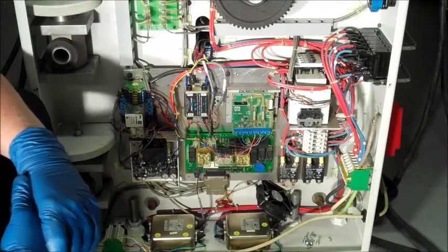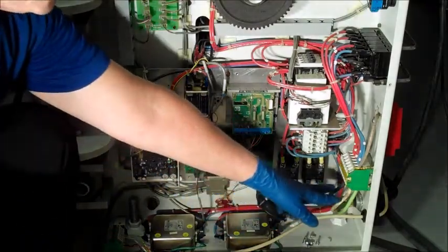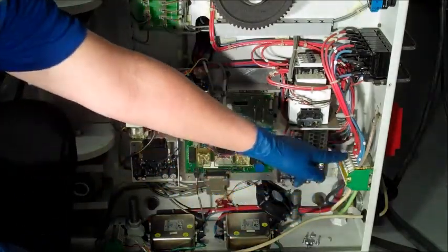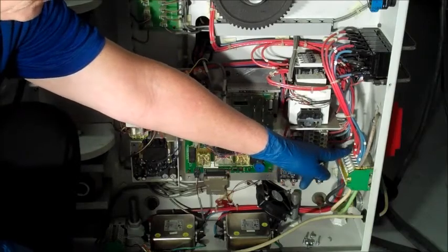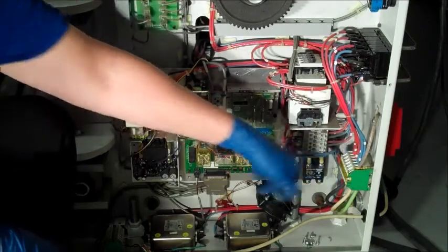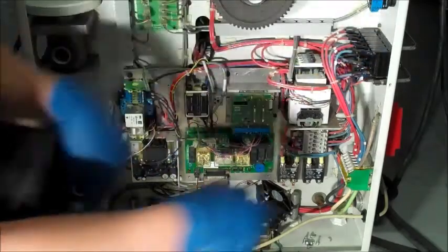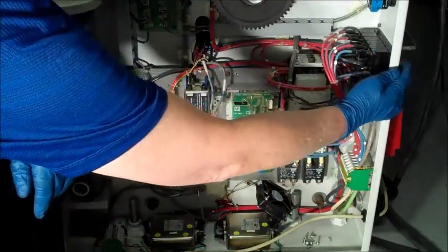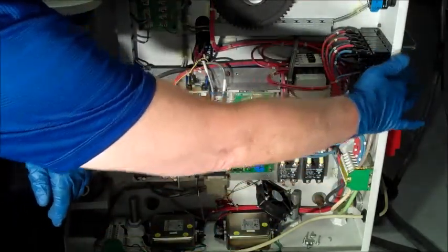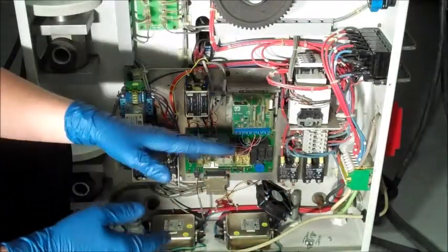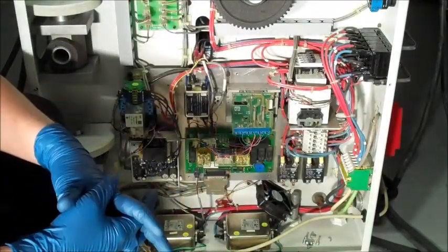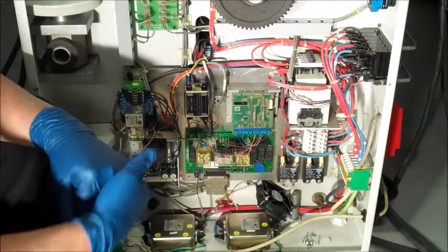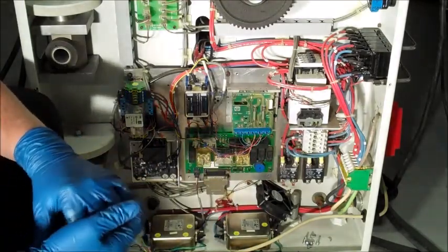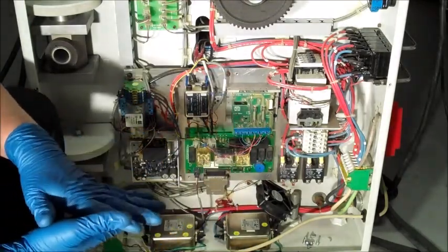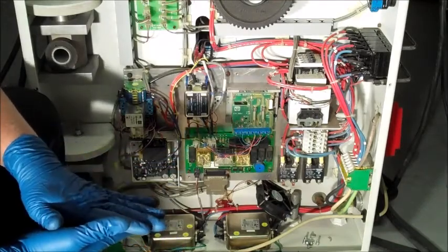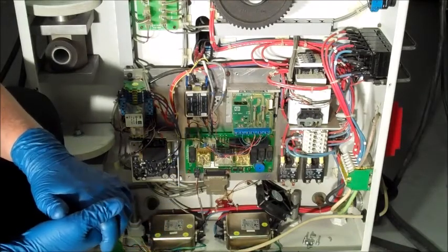But you can see after you come into your service block here, your AC splits off into a blue and a red, and then your main power switch on this unit is actually also a circuit breaker. Works the same exact way on the Orca. So when you energize the circuit breakers, you energize your heating circuits and your drive circuits and your safety circuits.